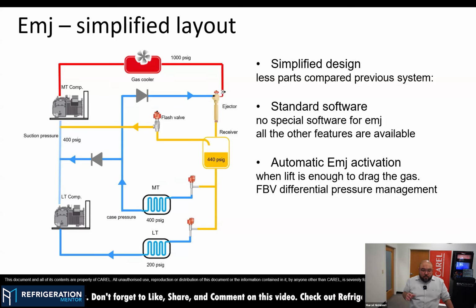This is another advantage of this new layout: the ejector functions are already present in the standard software, so there is no new custom software dedicated just to the ejector. Since the ejector mainly operates as an HPV valve, you will see the ejector's percentage opening and closing as the HPV valve. For a technician who already knows CAREL controls, it will be easy going because there is no special software for that, and everything is in the same package. For the new solutions with the Ejector Manager, there will be a dedicated controller where you can check all the electrical and all the parameters related to transcritical valve control, and one of these valves would be the ejector.